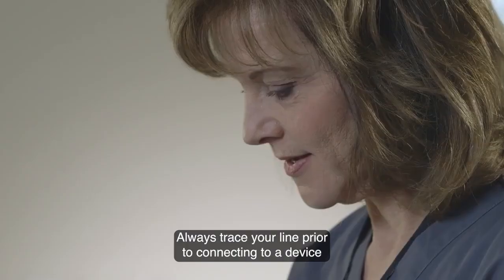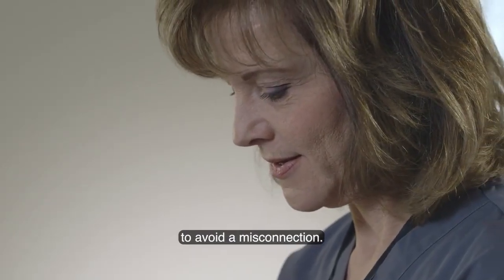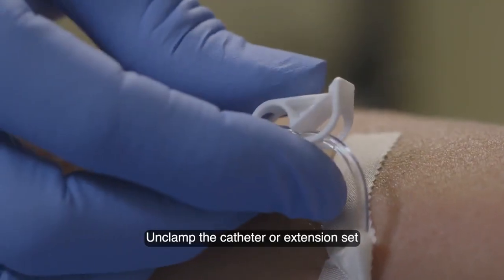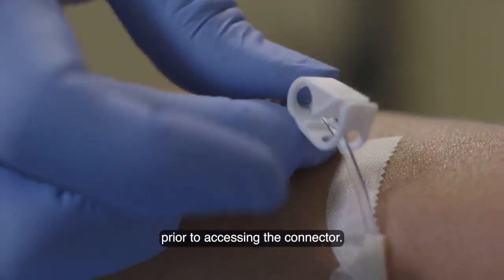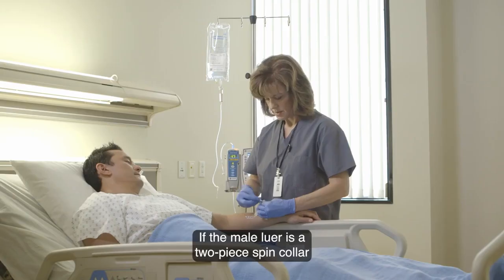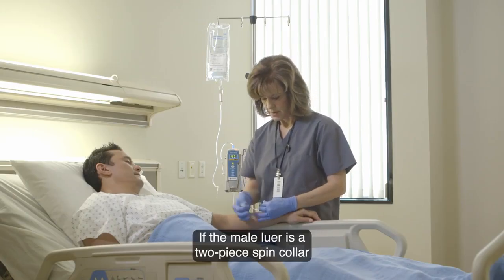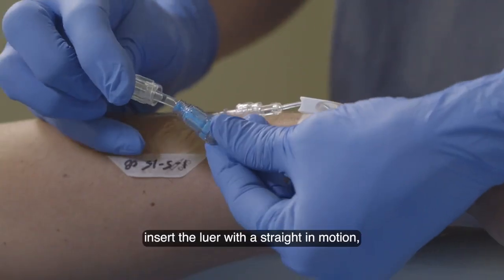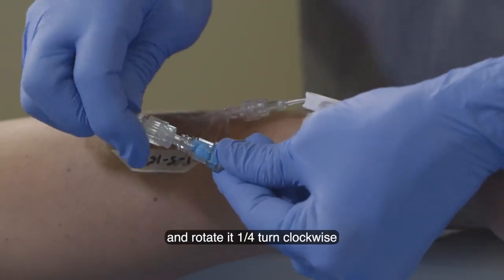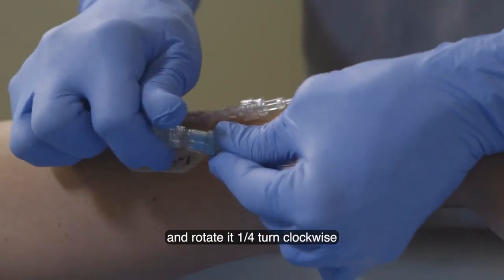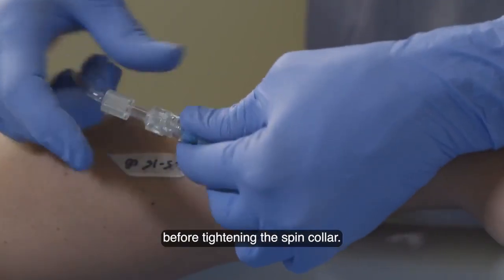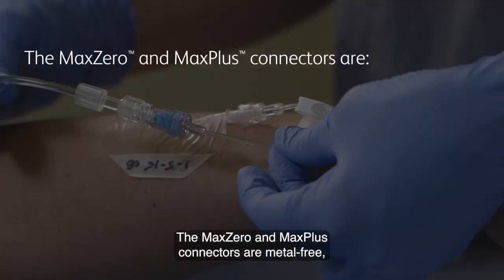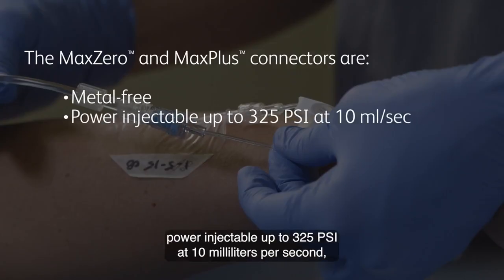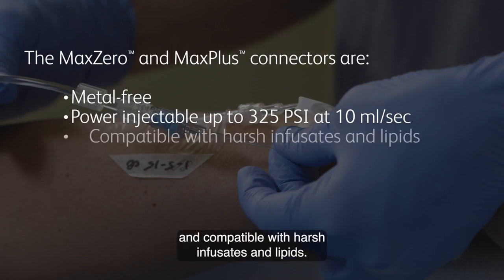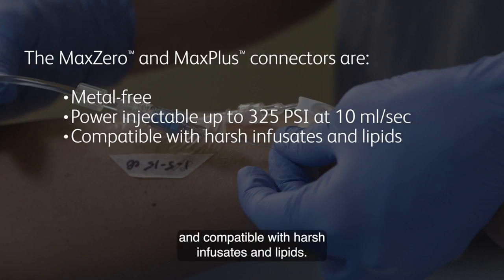Always trace your line prior to connecting to a device to avoid a misconnection. Unclamp the catheter or extension set prior to accessing the connector. If the male luer is a two-piece spin collar, pull back the collar. Insert the luer with a straight-in motion and rotate it 1/4 turn clockwise before tightening the spin collar. The MaxZero and MaxPlus connectors are metal-free, power injectable up to 325 psi at 10 milliliters per second, and compatible with harsh infusates and lipids.